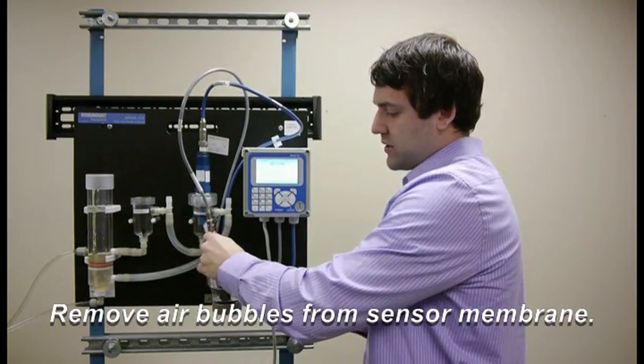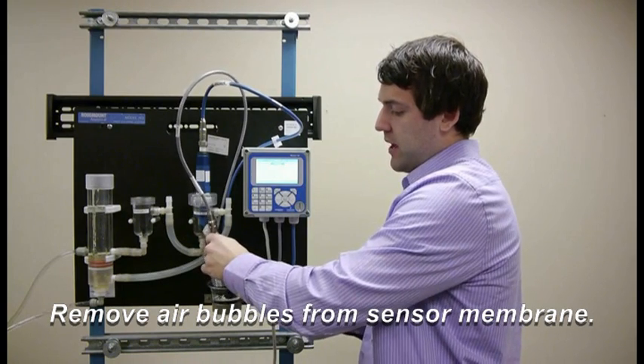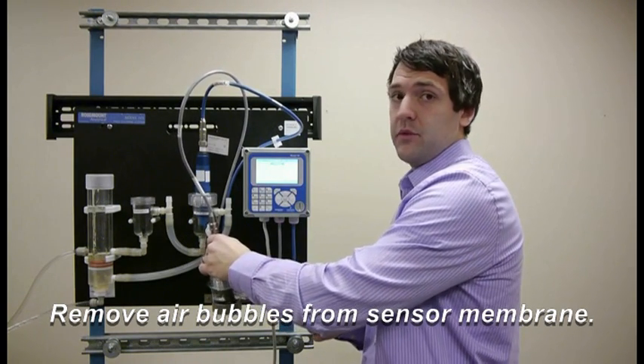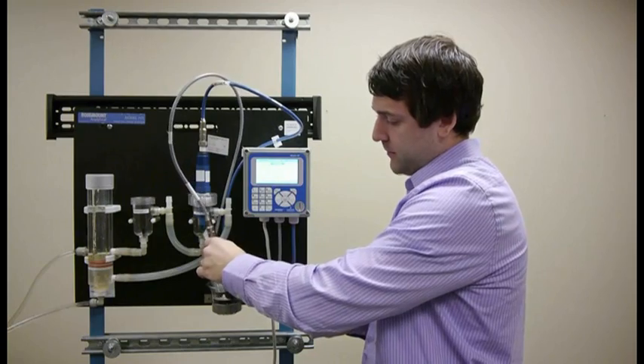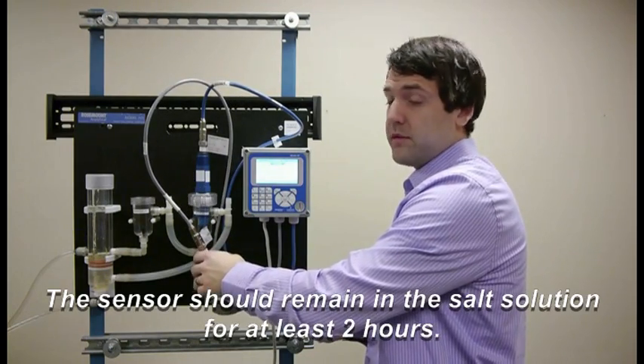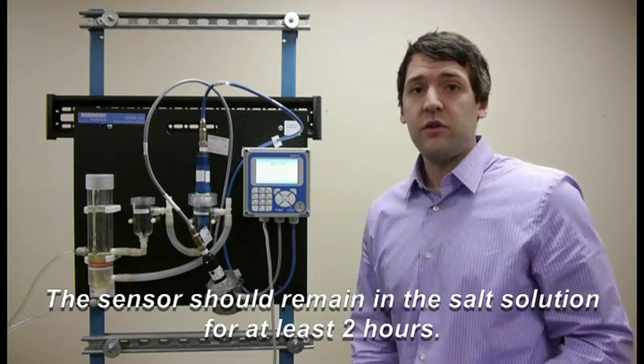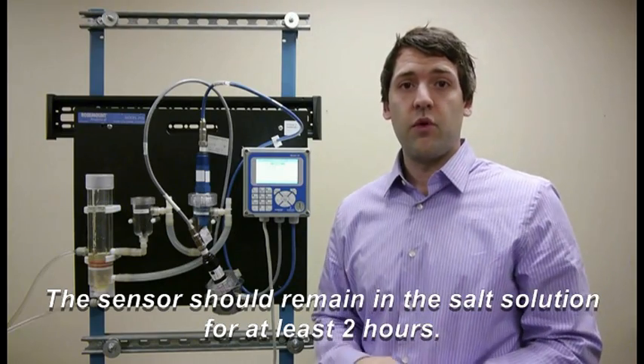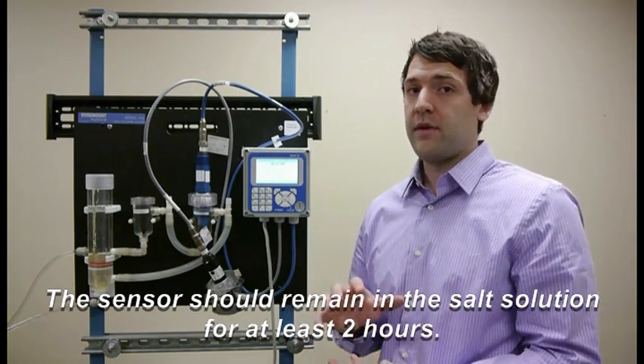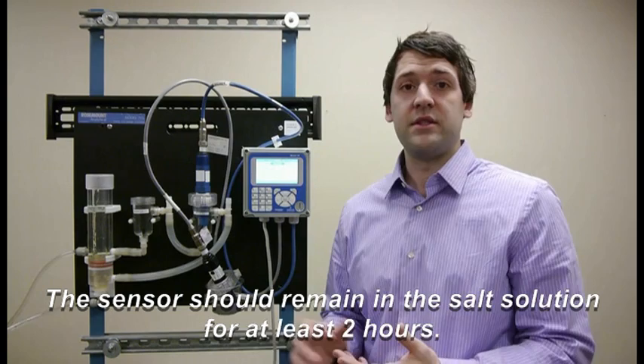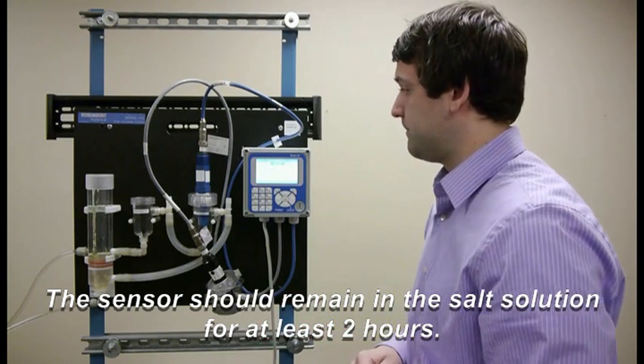Now you're going to need to swirl the sensor around a few times so that no air bubbles are trapped in or on the membrane head. Then you're going to leave it in there for a minimum of 2 hours. We recommend that you do this maybe at the end of the day, and then you come back in the morning and you have a solution that's ready for you, and you can then zero the sensor.